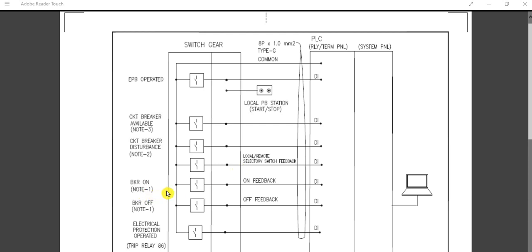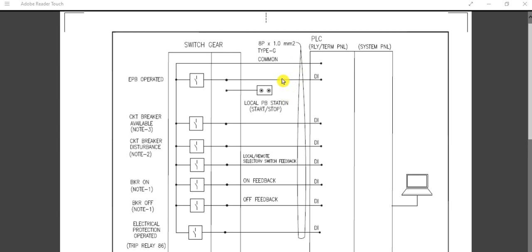Next are breaker ON status and breaker OFF status — these are the breaker ON feedback and breaker OFF feedback signals, each as individual DI signals. Also, electrical protection operated — basically trip relay or 86 lockout relay operated — all these signals are considered as DI feedback signals to the DCS or PLC cabinet.